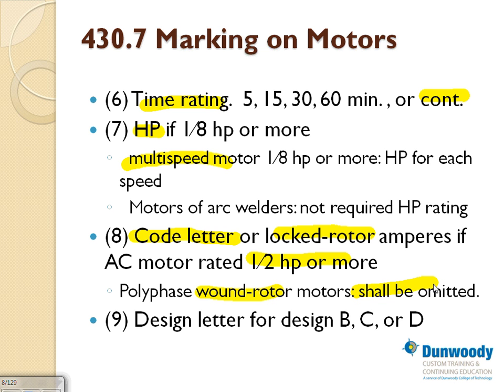That drives people nuts. So, for example, if you have a wound rotor motor, has anybody worked on a wound rotor motor? A lot of these equipments, guys, are not with the advent of the VFD. This was another good motor that you could speed control. With the advent of the VFDs, induction motors are becoming superior. Even DC motors still have their application. But with induction motors, if you have a VFD on any piece of equipment, you can speed control it. That's why DC was superior to AC for a long time, motor-wise, because of speed control. VFD solved this problem. Design letter: B, C, or D. 90% of the equipment that you guys are going to be designing is going to be design B. It's a kind of general design code.